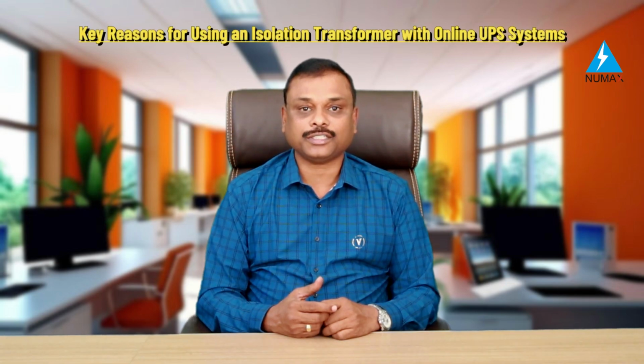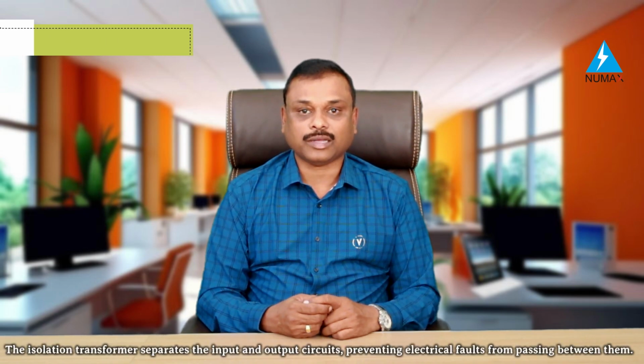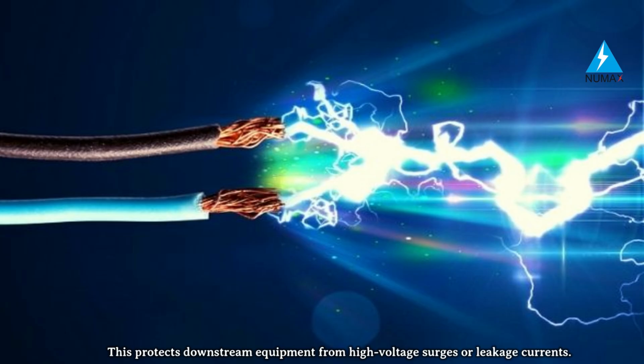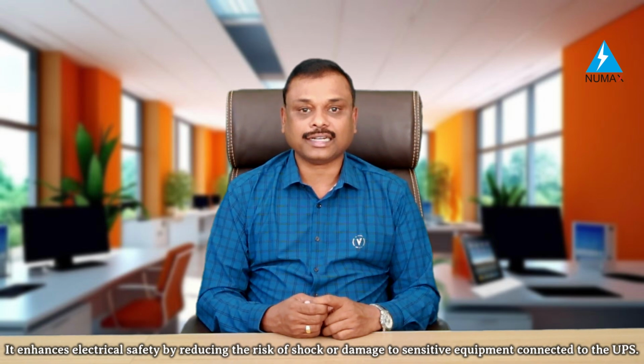Key reasons for using an isolation transformer with an online UPS system. 1. Electrical isolation for safety. The isolation transformer separates the input and output circuit, preventing electrical faults from passing between them. This protects downstream equipment from high voltage surges or leakage currents. Benefits: it enhances electrical safety by reducing the risk of shock or damage to sensitive equipment connected to the UPS.